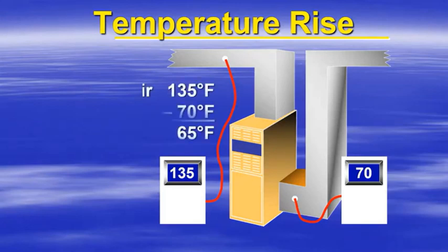Taking our return air temperature and our supply air temperature - in this example we have a 70 degree return air and 135 degree discharge air. We take these two numbers and subtract them to get our temperature rise of 65 degrees.